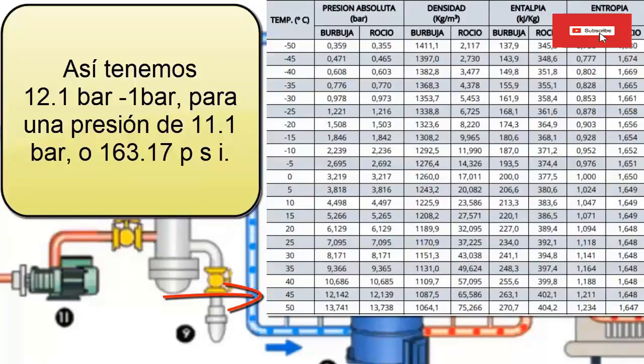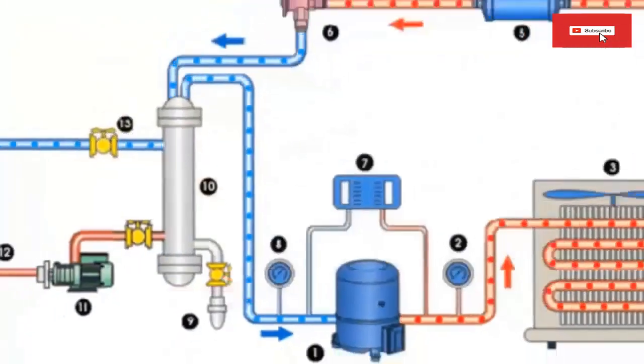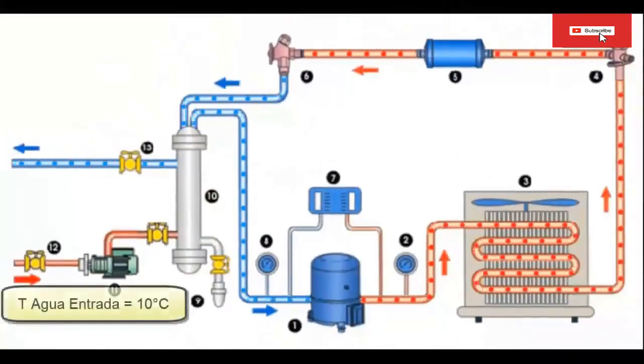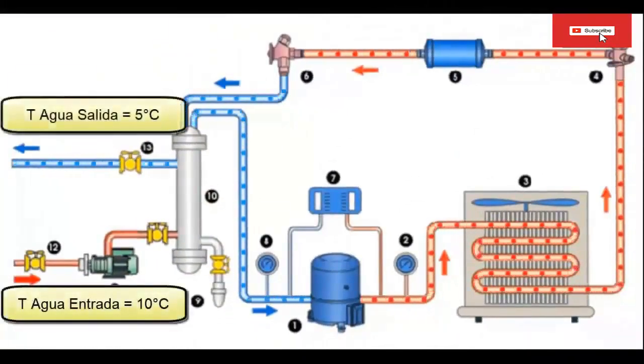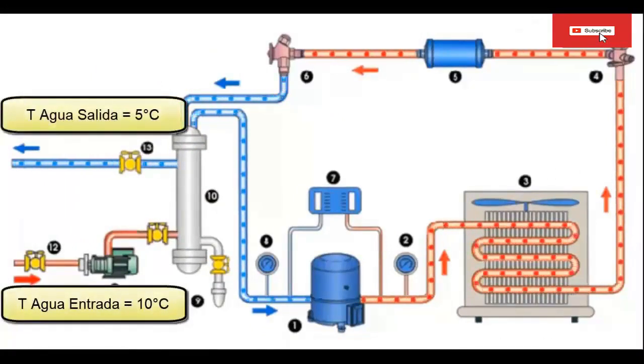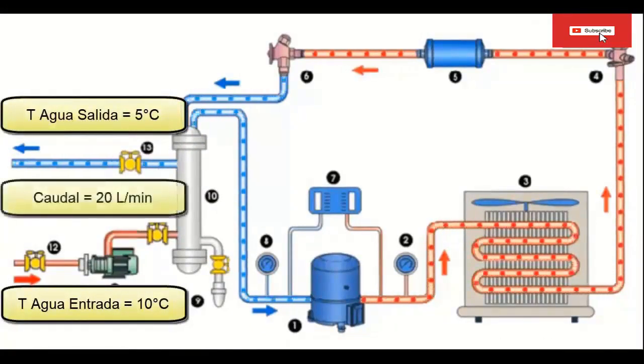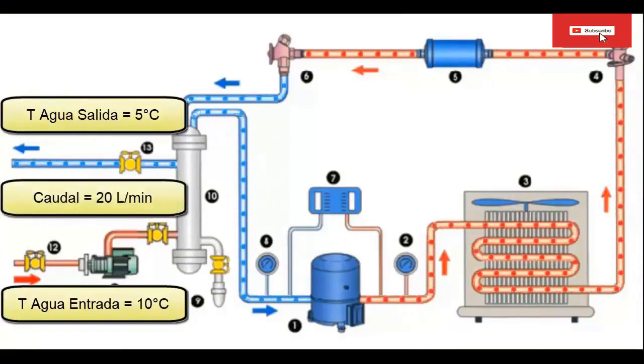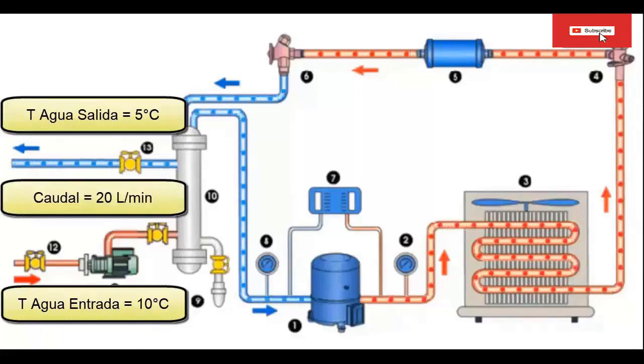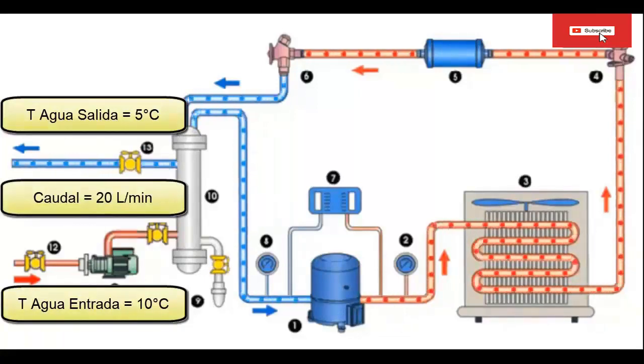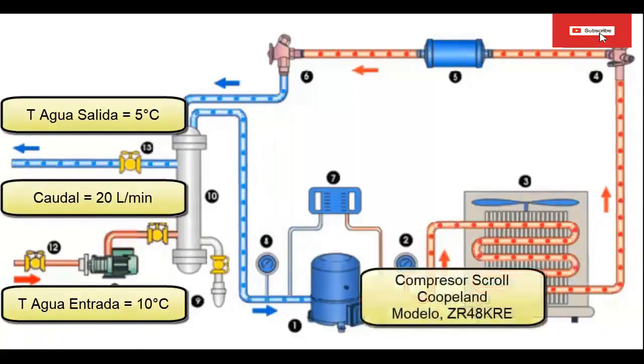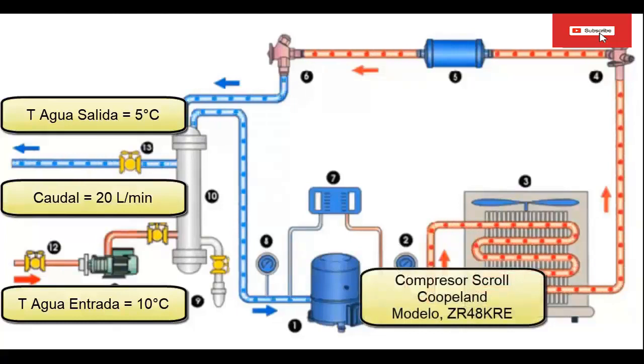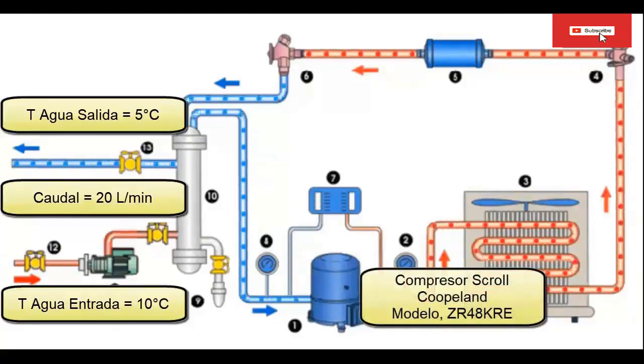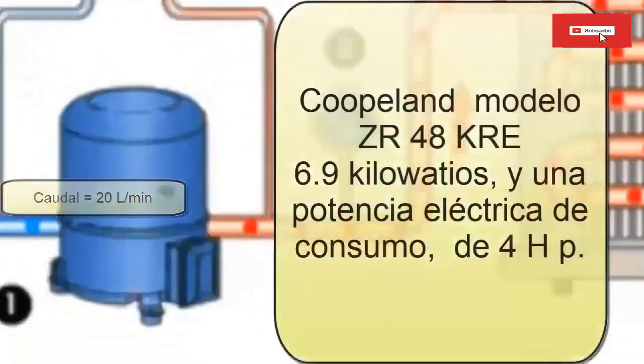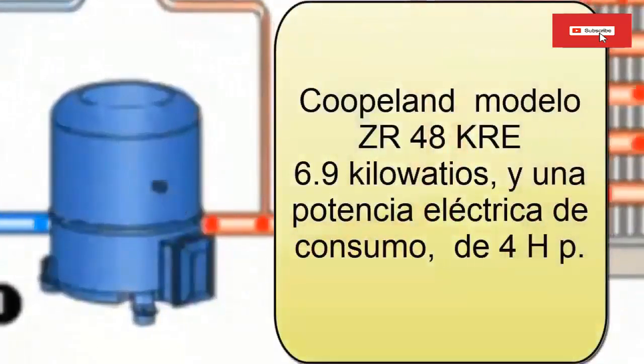163.17 psi. The water that we are cooling arrives at a temperature of 10 degrees Celsius and leaves at a temperature of 5 degrees Celsius. An average of 20 liters of water are being cooled per minute. The cooling load is constant, so the system does not have important control strategies. The compressor that the equipment is using is a Copeland scroll compressor, model ZR48KRE, with a cooling capacity of 6.9 kilowatts and an electrical power consumption of 4 HP.